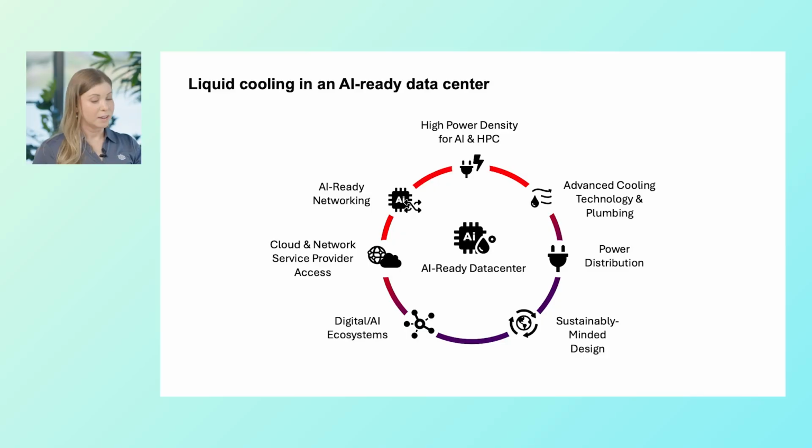liquid cooling? Yeah, so I'd say the biggest challenge is, if a customer, for example, is trying to do this on-prem, there are so many components you have to think about now. Essentially liquid cooling is plumbing. So now you have to consider plumbing in your facility and the power as well. And we're talking cabinets that are over 100 kilowatts now for GPU workloads.